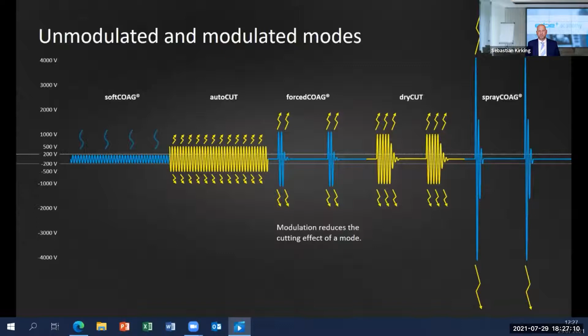This serves to achieve a more intensive coagulation seam than with the unmodulated autocut. And lastly, the spray coag uses extreme peak voltage of several thousand volts to produce these longer sparks for a short sort of brush effect. To prevent it from cutting, these high voltage modes are highly modulated. That means the pulse is very, very short. Technically, the modulation of such modes is given with the duty cycle or the crest factor.